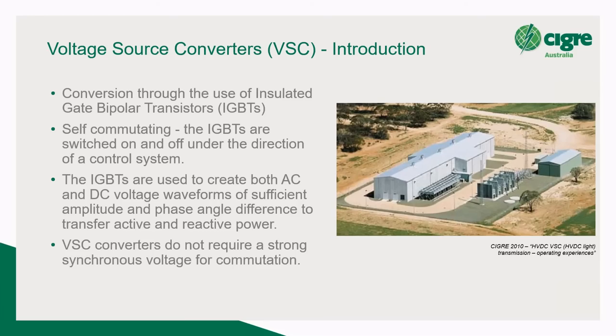Now, VSC converters do not require a strong synchronous voltage for commutation. Now, this means they're popular in low AC system strength applications. They can be used to black start a network if you design it appropriately. So you put an auxiliary supply in there so you can run your control system, your cooling pumps, you create your own AC modulating waveform instead of the controls taking one from the network. That's pretty much one of the reasons why they're so popular.